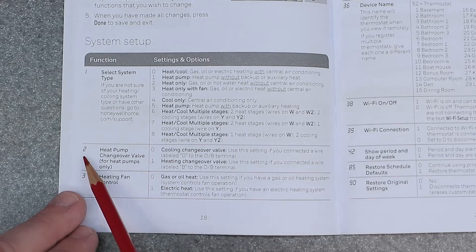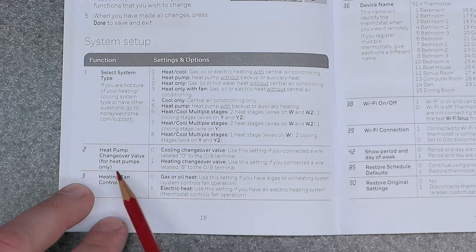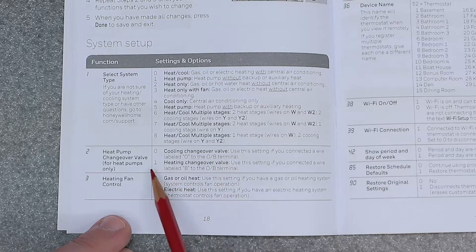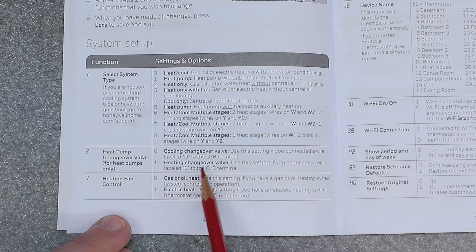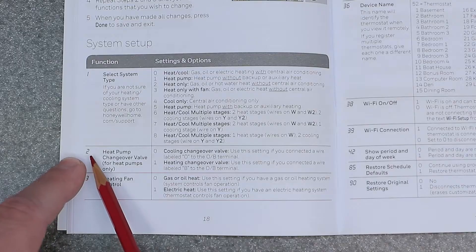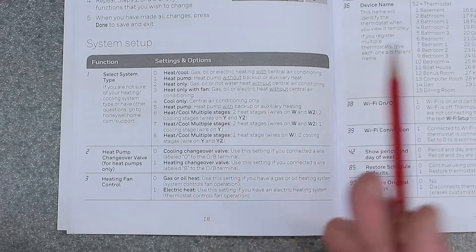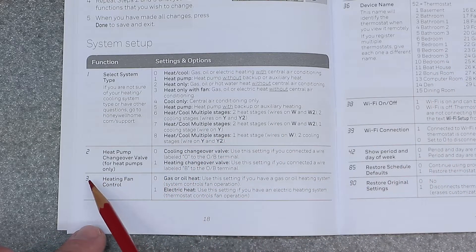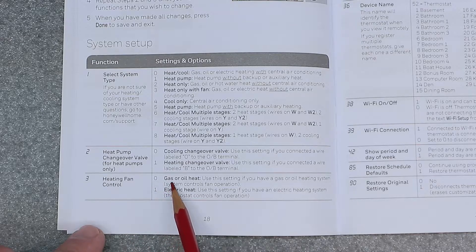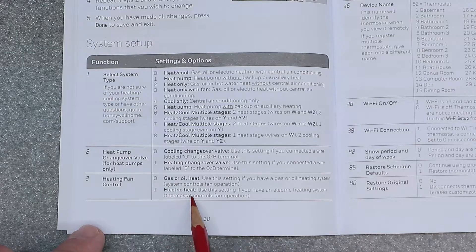Over to number two is heat pump changeover valve for heat pumps only. So we have zero is cooling changeover valve and one heating changeover valve. So like I said, this number here on the left is the number on the left on the screen. This option here is the one on the right. So number three is heating fan control. Zero equals gas or oil heat. One is electric heat.